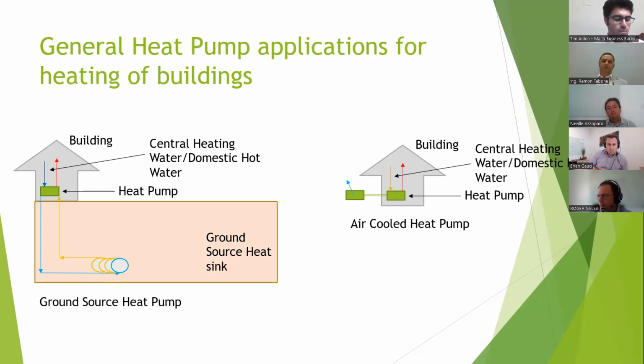Basically, we have two typical installations of heat pumps. On the left, we have the ground source heat pump. A heat pump is basically a refrigeration unit, similar to an air conditioning unit. What we do is we give electricity to the heat pump. We take away the heat for our use, to heat the building, to heat hot water, and the cold side is dissipated into the ground for the ground source heat pump.